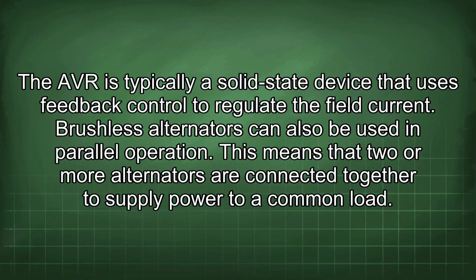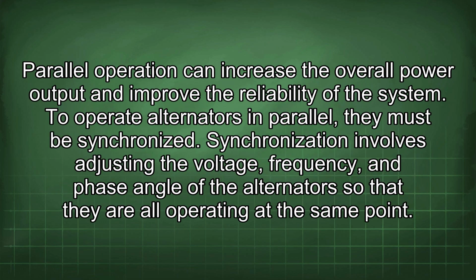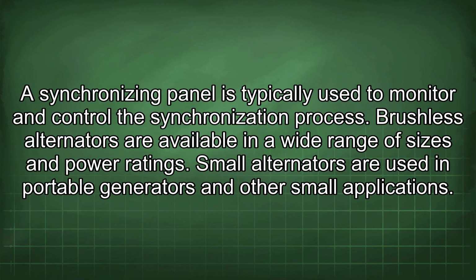Brushless alternators can also be used in parallel operation. This means that two or more alternators are connected together to supply power to a common load. Parallel operation can increase the overall power output and improve the reliability of the system. To operate alternators in parallel, they must be synchronized. Synchronization involves adjusting the voltage, frequency, and phase angle of the alternators so that they are all operating at the same point. A synchronizing panel is typically used to monitor and control the synchronization process.